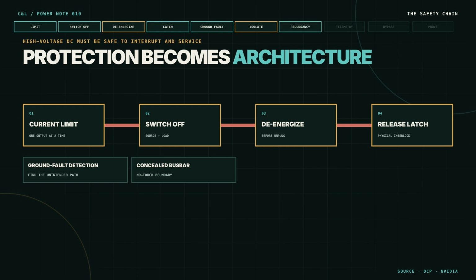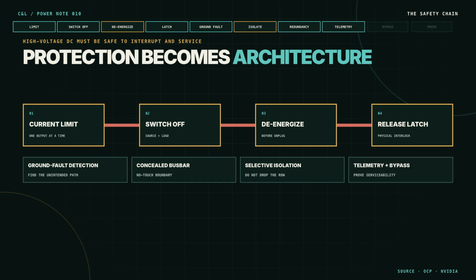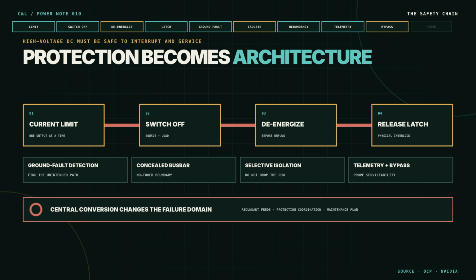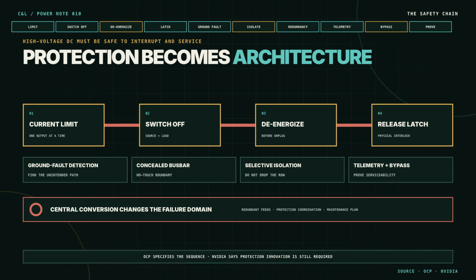NVIDIA likewise places protection between the power room, hall, row, and rack, while acknowledging that overcurrent protection and serviceability need innovation. Central conversion may remove many small power supplies, but it changes the failure domain. Designers still need redundant feeds, selective isolation, telemetry, maintenance bypass, and proof that one fault cannot remove a compute row.